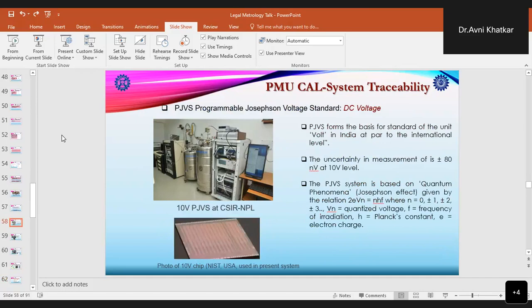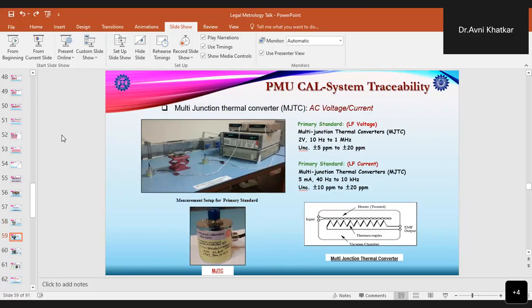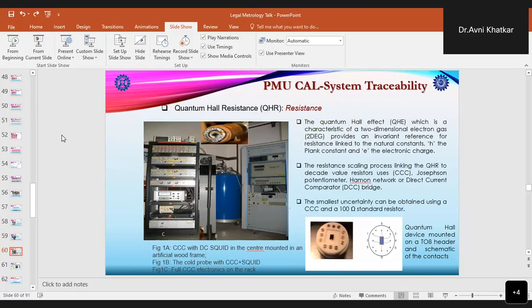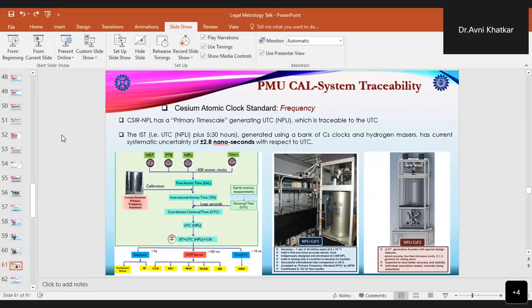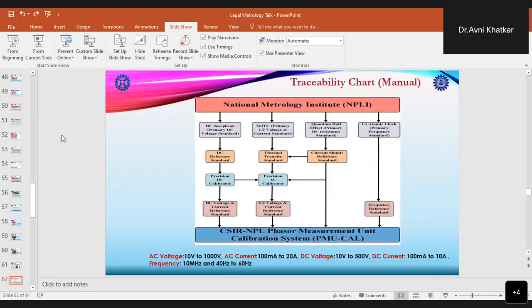So just to see a glimpse, this is the PJVS, that is, programmable Josephson voltage standard, for the DC voltage traceability of the system. These are the MJTCs for the AC voltage and current. For the resistance, we have the quantum Hall resistance standard. For the frequency, we have cesium atomic clock standards. This chart shows the traceability chart of the PMU calibrator system: AC voltage range from 10 volts to 1000 volts, AC current from 100 milliamperes to 20 amperes, DC voltage 10 volts to 500 volts, DC current 100 milliamperes to 10 amperes, and frequency at 10 megahertz and from 40 hertz to 60 hertz.